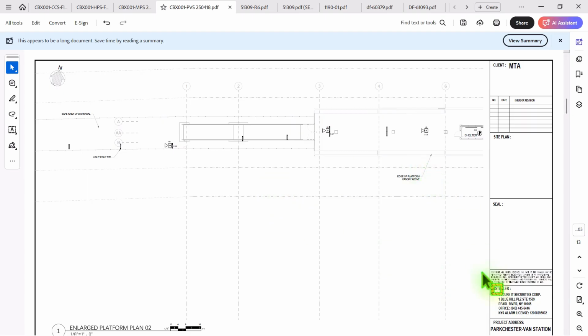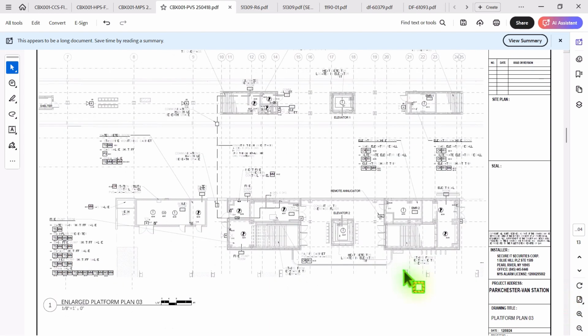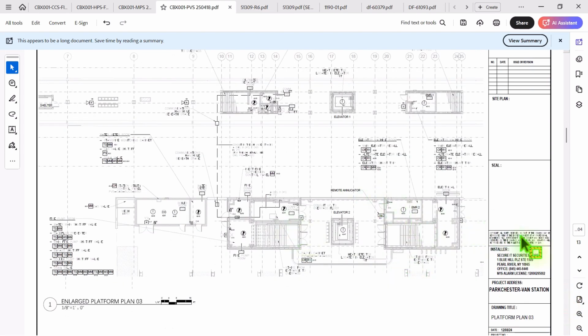You'll see the layout I did when I marked up all the drawings, and I'll go over that too. I marked these up to identify what booth is going to be serving what and how the horn strobe is going to be laid out according to the wire. I didn't look at the conduit fill on these, but potentially in all areas it's going to be one cable for data, one cable for the horn strobes, then one cable connecting from the fire alarm control panel to the booster panel, and booster panel to booster panel to interconnect the two.